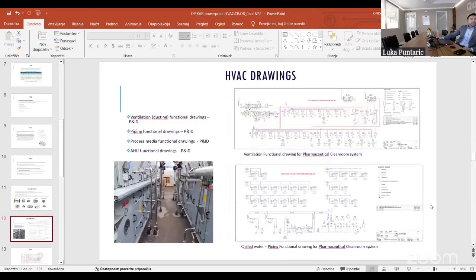Those are only examples of the HVAC drawings that we prepare when preparing the design of the project. So P&ID, piping and instrumentation design drawings, schematic drawings of all the piping, heating, cooling, steam, city water, all different piping elements, ducting, process media, process piping, GMP classified piping, and air handling units. Those are just examples of a recently executed pharmaceutical project in Belgium.